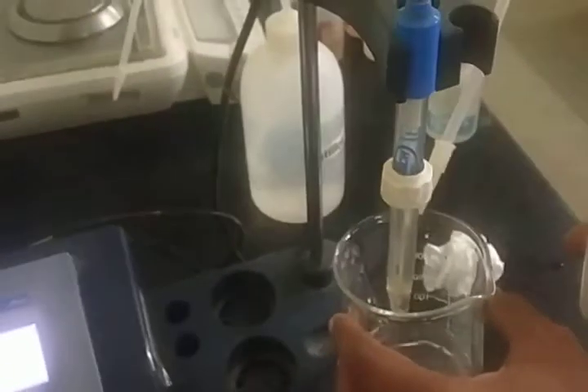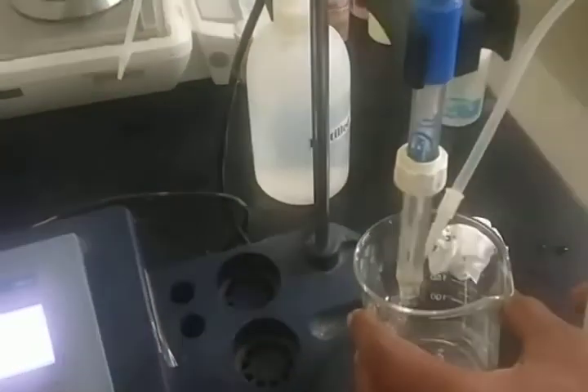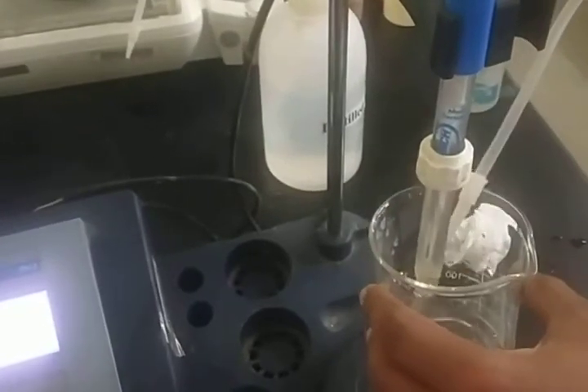Now we are going to place the third buffer. Before placing the third buffer solution, we need to rinse the electrode properly and thoroughly, and we need to clean it and wipe it gently using tissue paper. All the buffer solutions will be freshly prepared. Now the electrode is being immersed. So the pH of this buffer solution is 9.2.